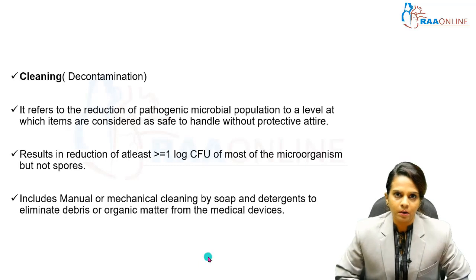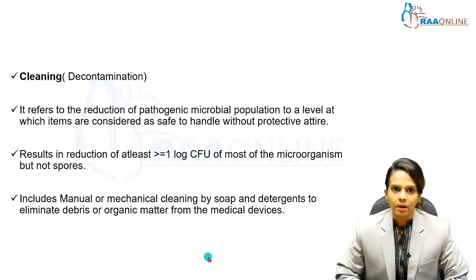So coming to cleaning. Cleaning is a decontamination process. It refers to the reduction of the pathogenic microbial population to a level at which items are considered safe to handle without protective attire. Whenever we feel that it is safe to handle without protective attire, this is called the cleaning process. It results in a reduction of at least 1 log colony forming units of most of the microorganisms, but not spores. It includes manual or mechanical cleaning by soap and detergents to eliminate debris or organic matter from the medical devices.